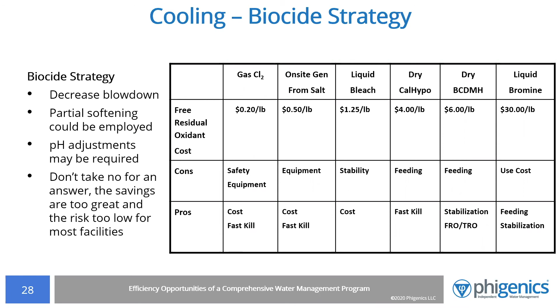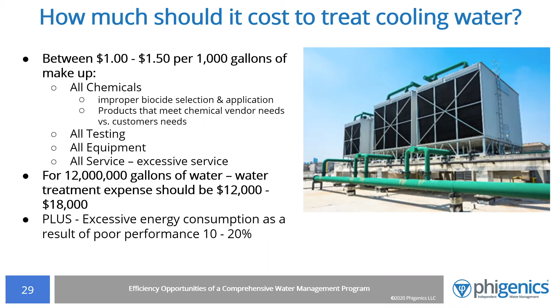So how much should it cost to treat cooling water? Between $1 and $1.50 per 1,000 gallons of makeup water for all chemicals, testing, equipment, and service. So for 12 million gallons of water, the water treatment expense should be $12,000 to $18,000 per year. This, of course, can vary from region to region, but it really is a reliable indicator. No matter your cost, if you are not tracking this number, you really don't know where you are.